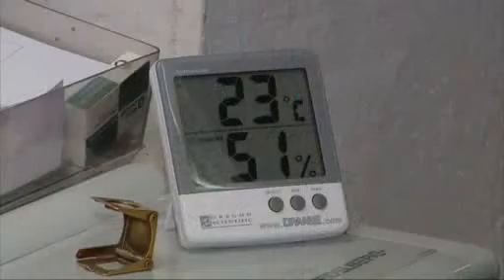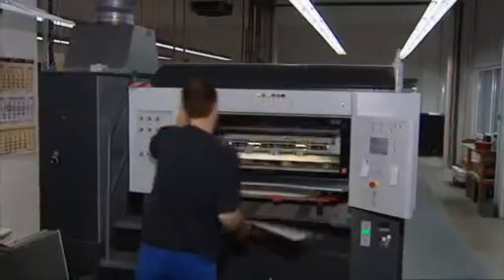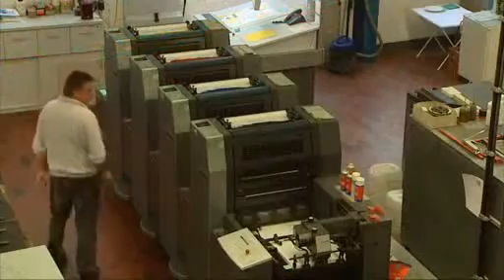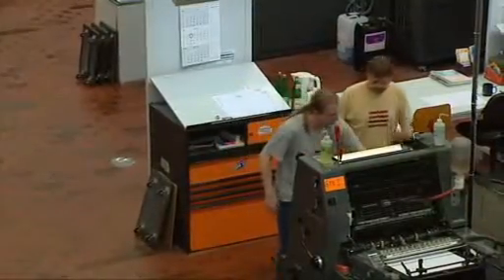The ideal humidity balance for processing paper is a relative humidity of between 50 and 60%. A modern humidification system can ensure a constant ideal relative humidity. This standardizes the printing process, reduces spoilage, avoids press down times, cuts production times, and in the final analysis cuts costs and keeps the customer happy with a perfect printing result.